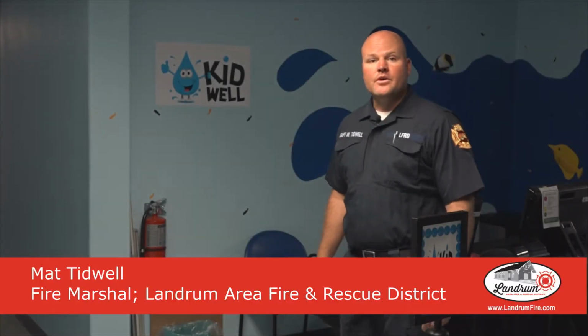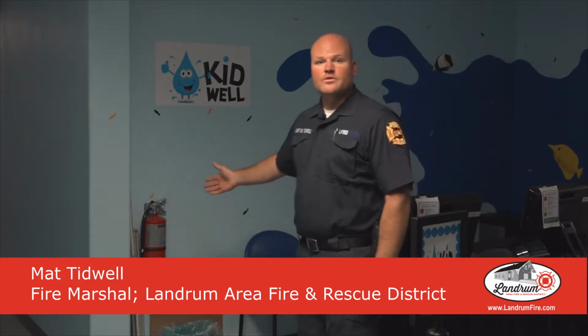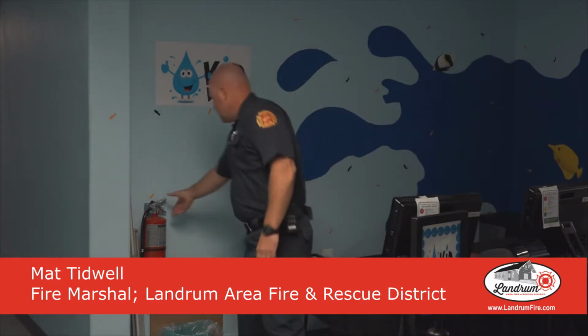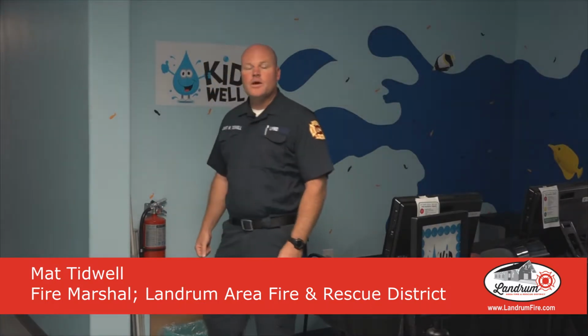Making our way around the structure, looking for another fire extinguisher. I was getting a little concerned, but we found one on this wall. It's properly mounted, it's secure, it's in the green, and it's due October of 2019 for inspection.